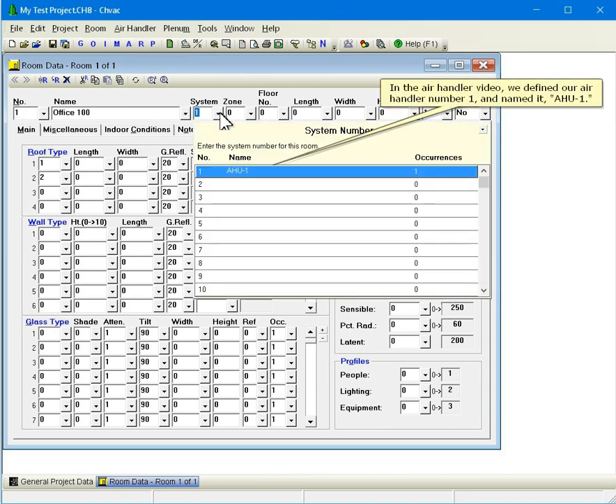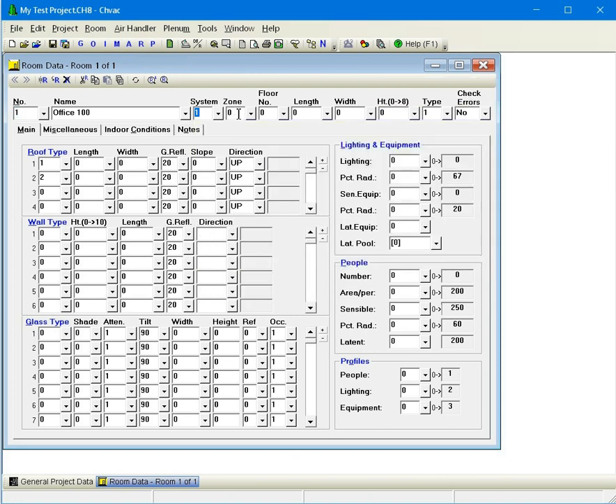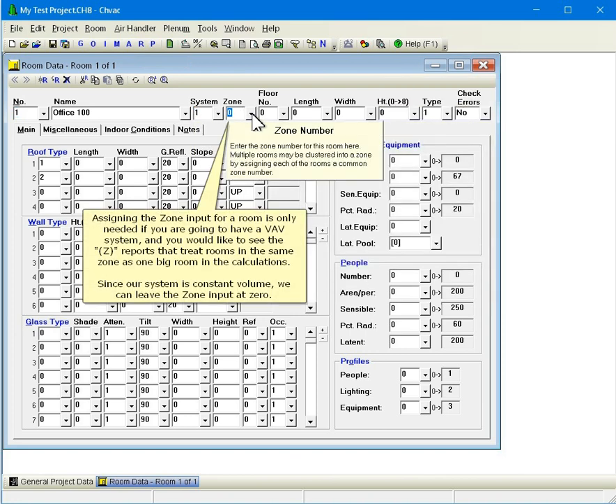In the air handler video, we defined our air handler number 1 and named it AHU1. Assigning the zone input for a room is only needed if you're going to have a VAV system, and you would like to see the Z reports that treat rooms in the same zone as one big room in the calculations. Since our system is constant volume, we can leave the zone input at 0.